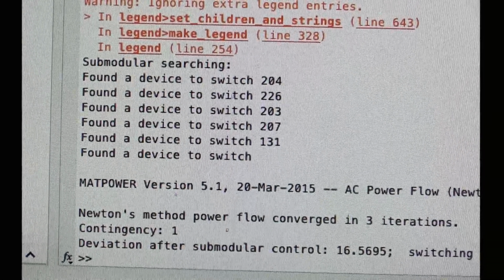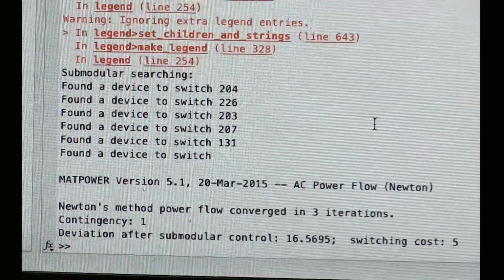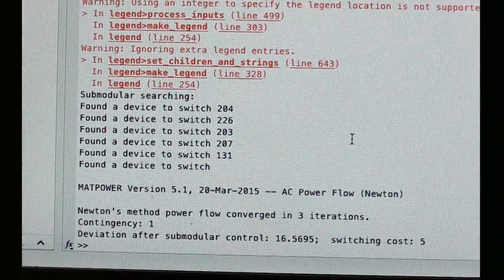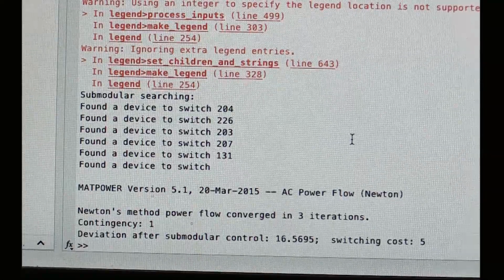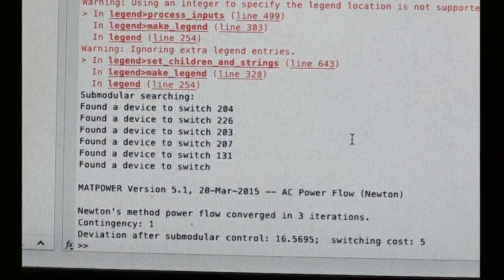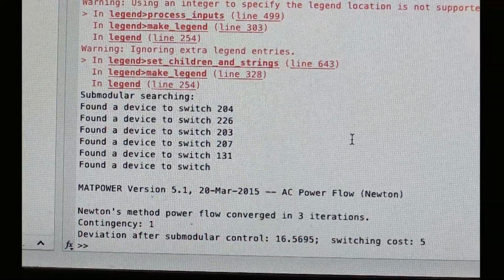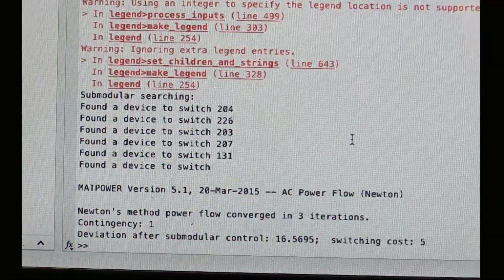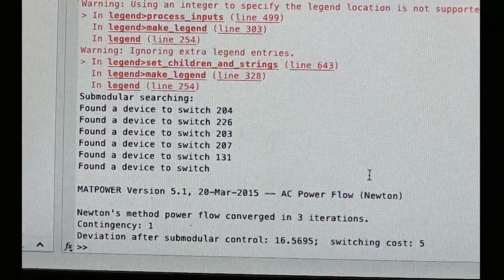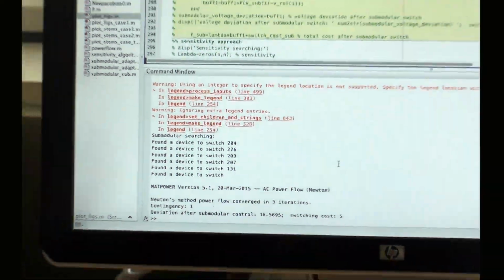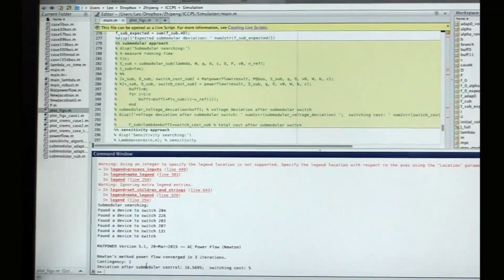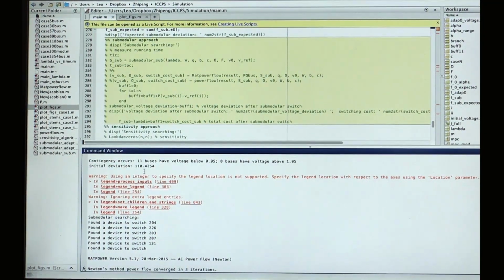Now we get a result. There were 11 buses having low voltage before, and it selects 5 buses to inject reactive power. These 5 buses are different from those having low voltage. We can observe that the deviation after our submodular control is lowered a lot. Initially, the deviation is over 100, and now it's lowered to 16 with only 5 switching cost.